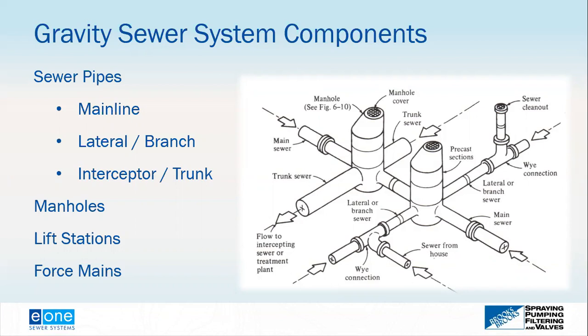With gravity sewers, the pipe is initially installed just below frost line at the highest point, but must slope continuously downward. At some point it becomes no longer economical or safe to dig a very deep trench, so a lift station is installed to lift the wastewater to a higher point, conveying it to either another gravity sewer or a force main. The need for lift stations and force mains is common in gravity sewer systems and depends on the topography.